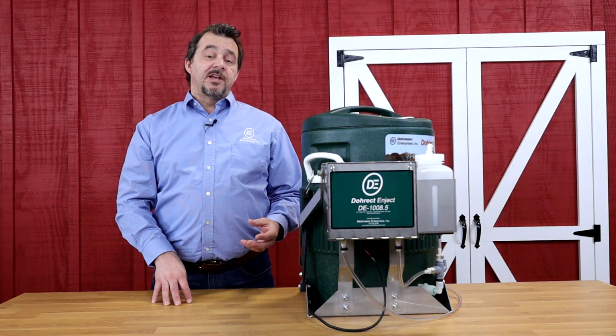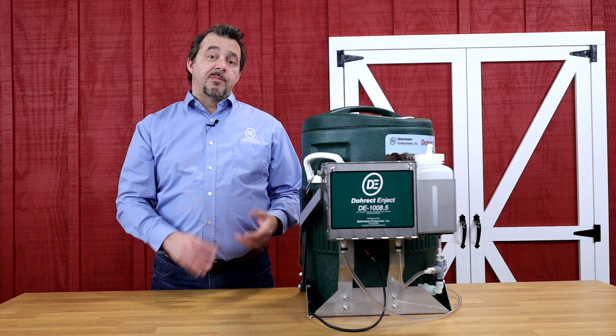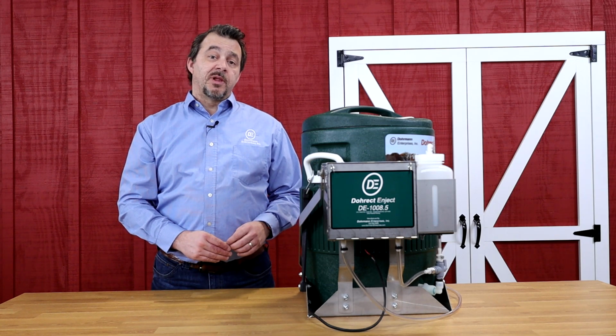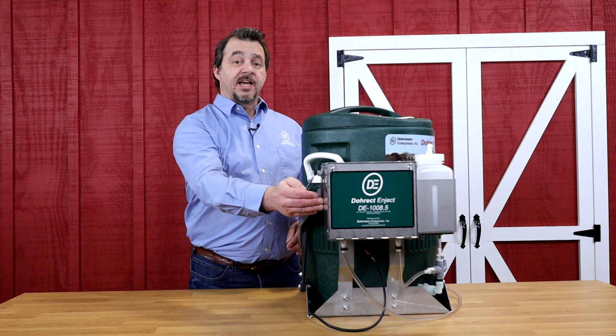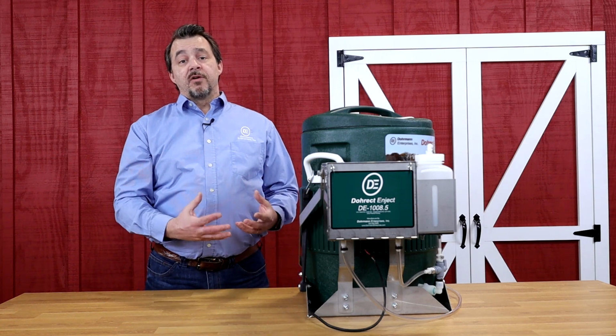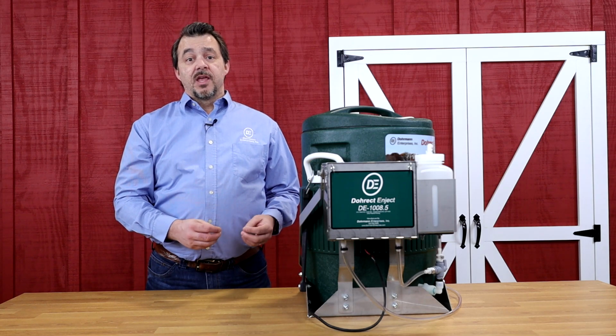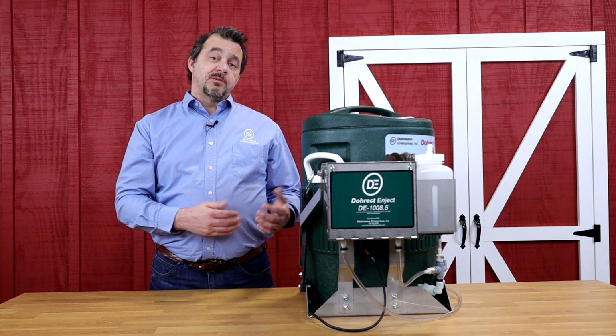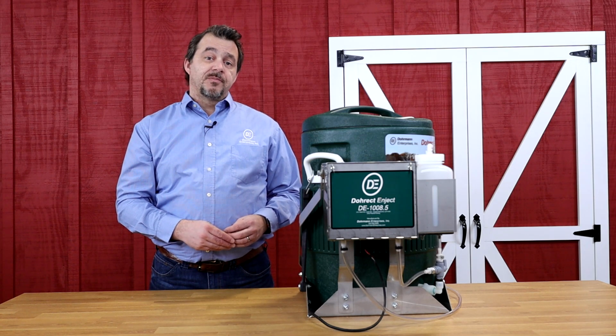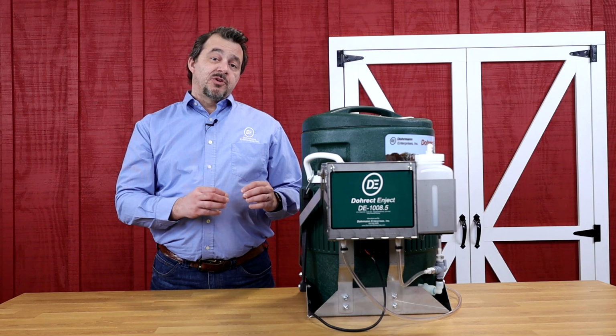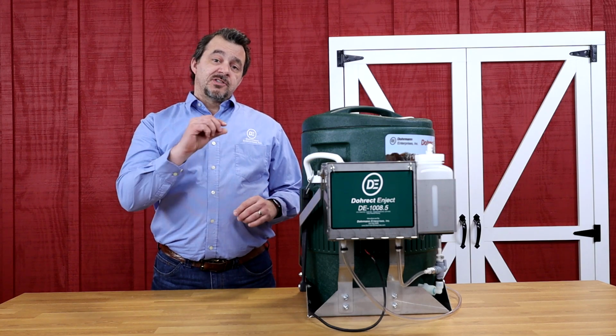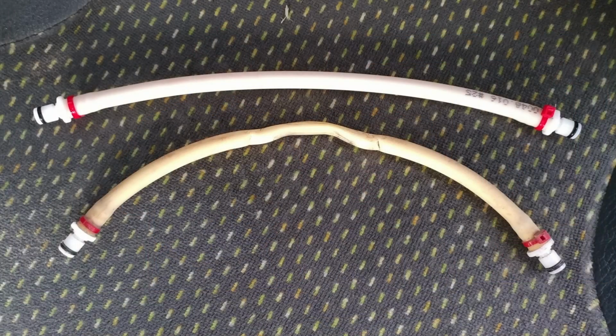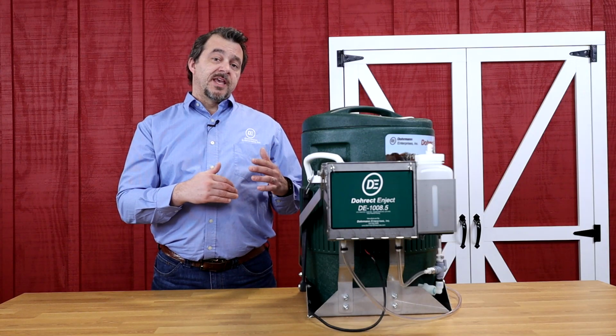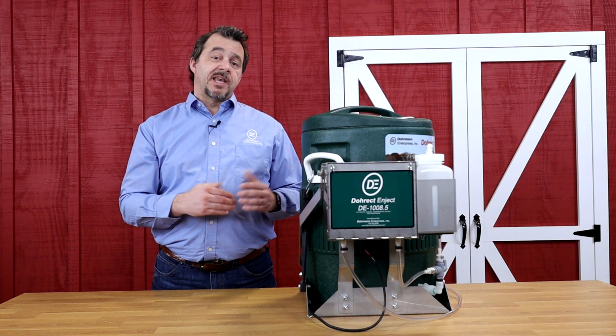process step by step. Next, we have to look at the pumping tube and determine when was that replaced last. The pumping tube is a wear part that is recommended to be replaced annually. It is located inside of the pump enclosure. We recommend that it's replaced at least annually, and for a lot of operators that are doing higher volumes, it may have to be replaced more often than that. And as you see, if the pumping tube has been in place for a while, what happens is the tube ends up becoming kind of squished and will retain a memory that way, and it does not allow the pump to get enough volume, or in some cases just simply not pump.